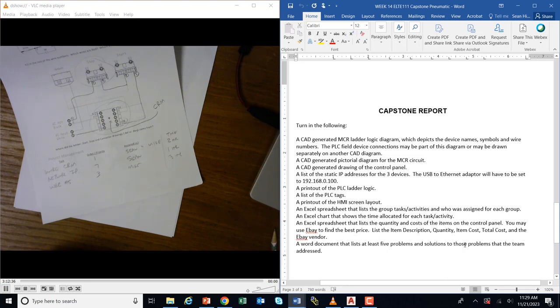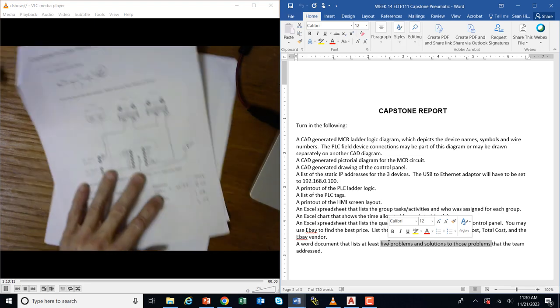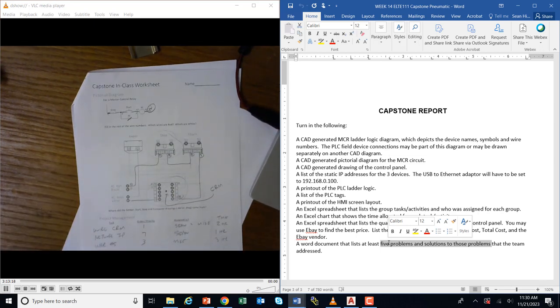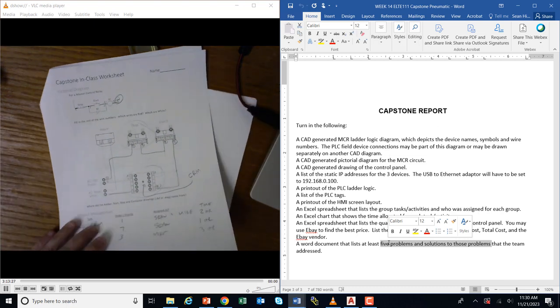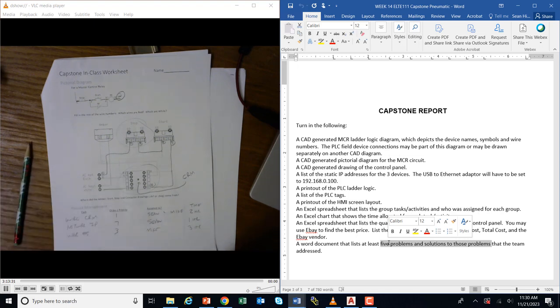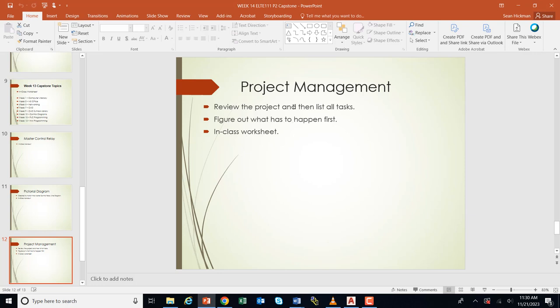You also need a Word document listing at least five problems and solutions that the team encountered. These need to be engineering or electrical problems requiring actual thought — not trivial things. For example: the relay kept chattering when we pushed start. Solution: we accidentally wired the holding contact through a closed contact instead of an open contact, causing it to open and close and chatter. The solution was to rewire it through an open contact. That's the kind of problem and solution I'm looking for.